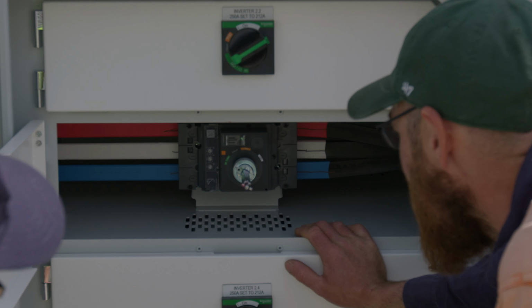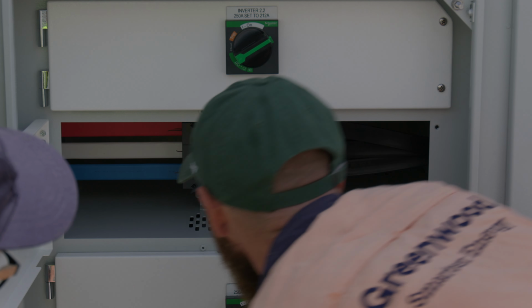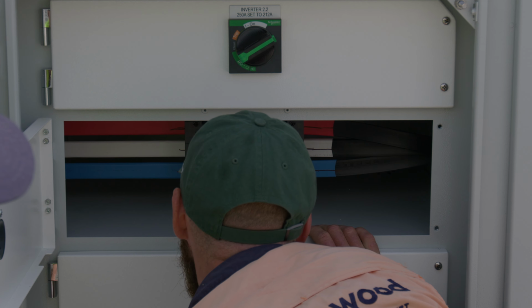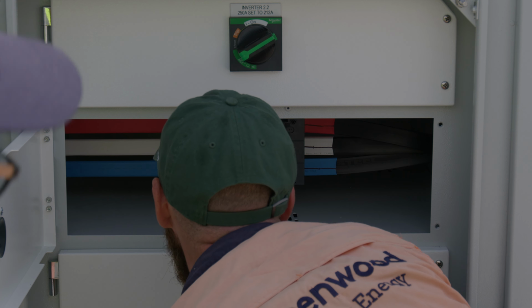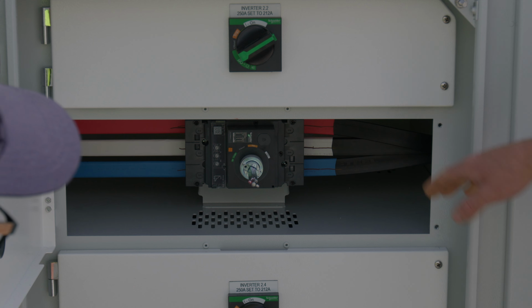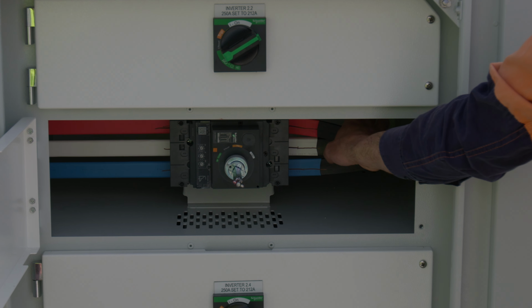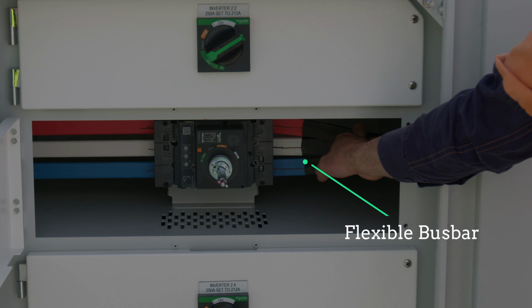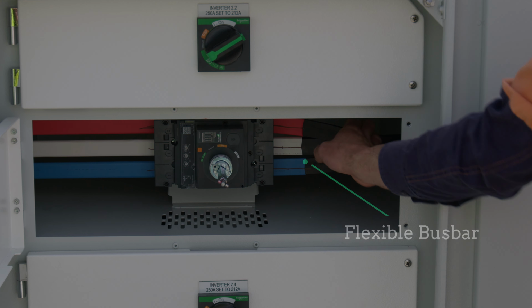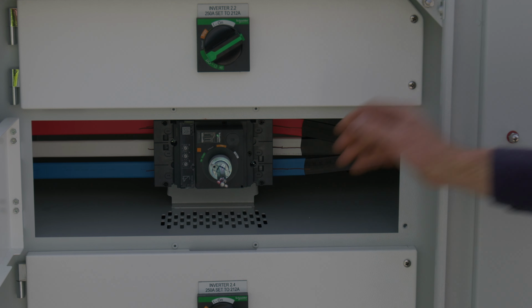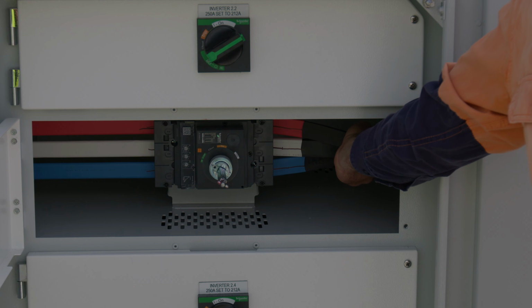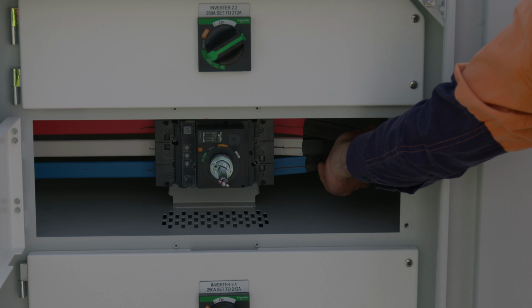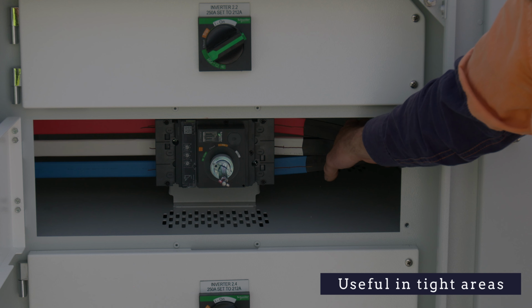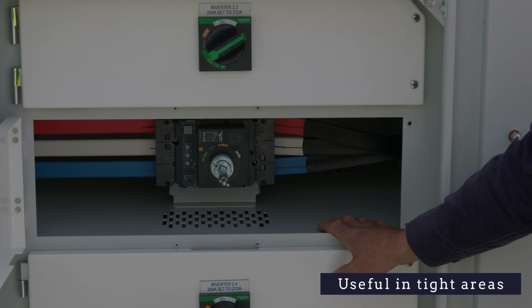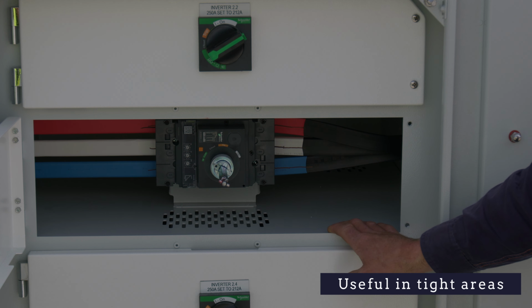So the connections to this particular breaker, they're not cable. They seem to be some kind of flexible... Yeah, so these connections here, this is a flexible bus bar. So this makes it easy to connect to the bus chamber, through wherever those bus bars are, without having to get bar work bent up. Flexible bus bar is incredibly useful in areas where the bar may have to bend around corners.